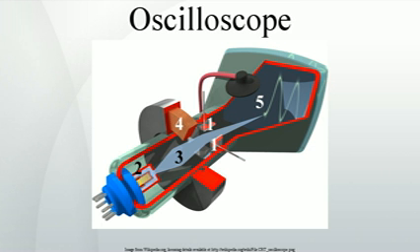A well-designed, stable, trigger circuit is required for a steady display. The chief benefit of a quality oscilloscope is the quality of the trigger circuit. Key selection criteria of a DSO, apart from input bandwidth, is the sample memory depth and sample rate. Early DSOs in the mid to late 90s only had a few KB of sample memory per channel.